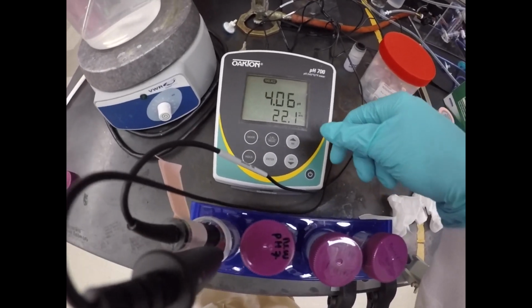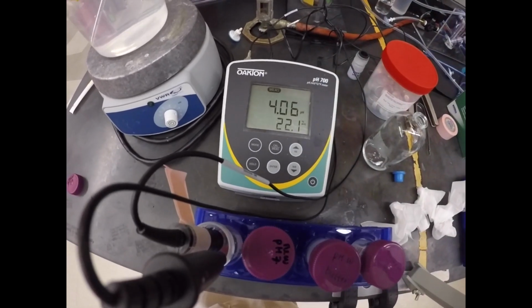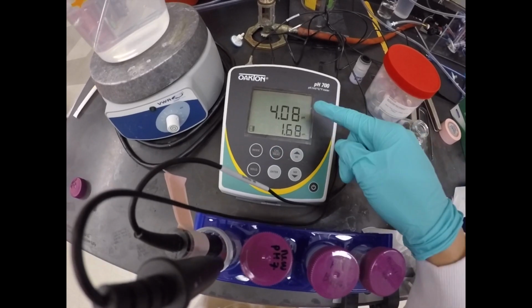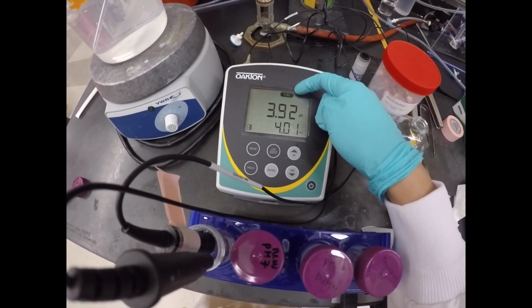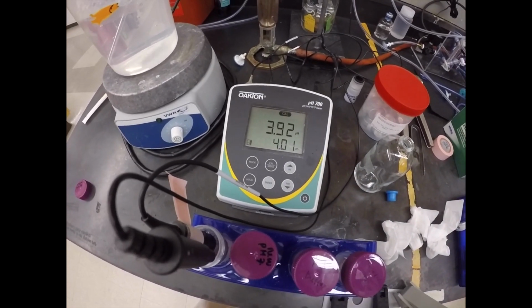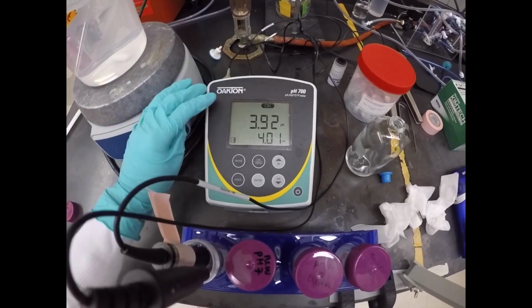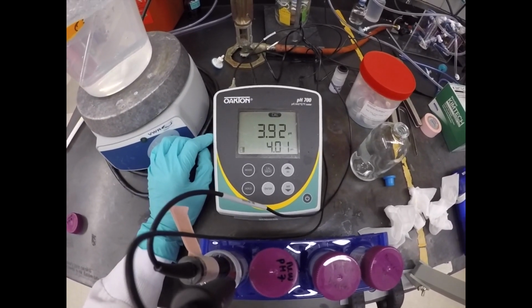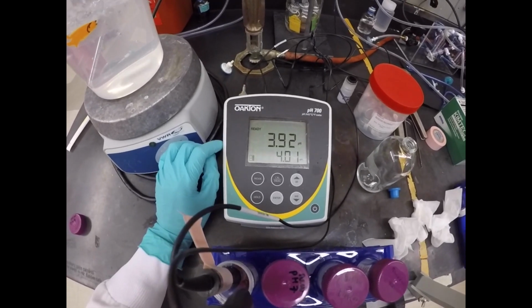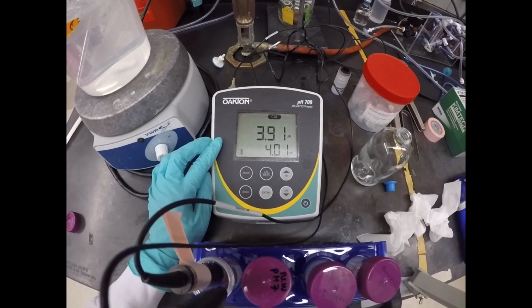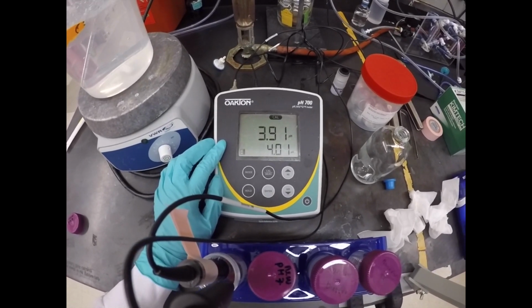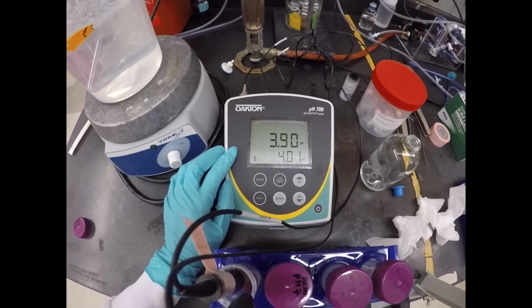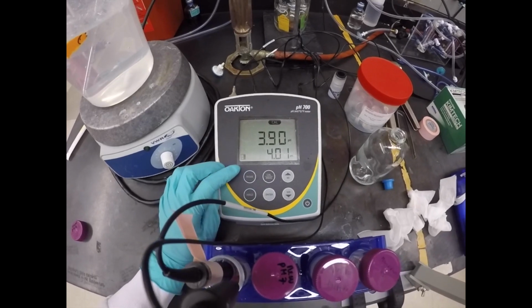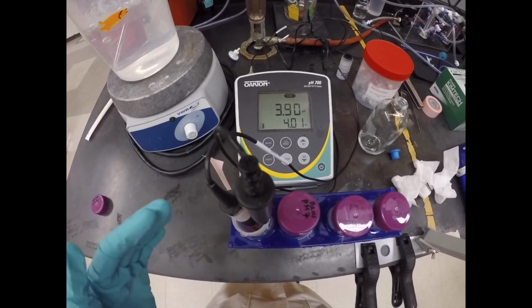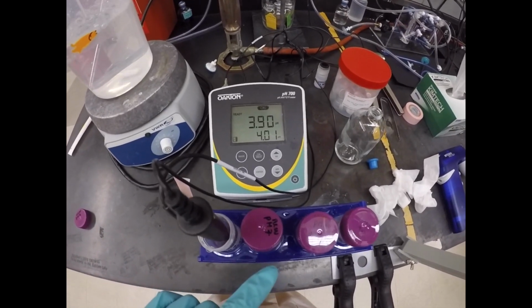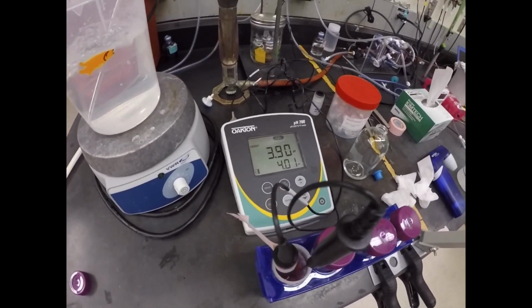So now what you do is you press Cal Mes to switch to calibration mode. And then you will see that it changed from measurement to calibration. And you just wait, give it a few seconds or minutes until the reading becomes stable. Once it shows the ready sign over here, that means that the reading is pretty stable. Disappeared again. Once the reading becomes stable, you're going to press enter, and then you're going to do the same rinsing step for both the pH probe and the temperature probe, and place the probes inside the other pH solution.